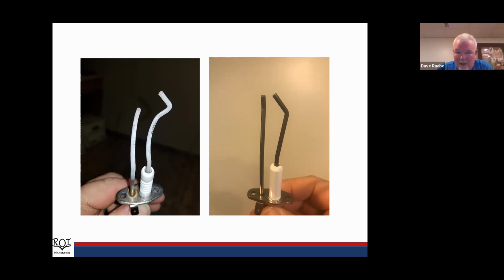And you can see how distorted that igniter was. And when it gets distorted like that, what happens is we can't light it at the proper place anymore. We may be sparking at the area all the way back at the base of that igniter. And what happens then is we fill the combustion chamber up with fuel before we ignite. It actually sounds like a gun going off. There's a pretty loud bang when it finally does light.